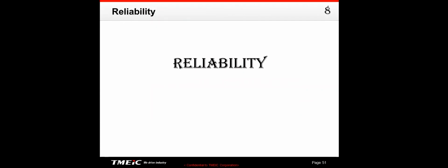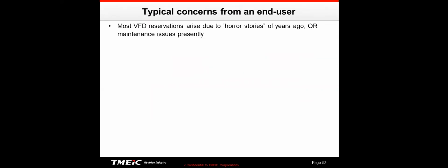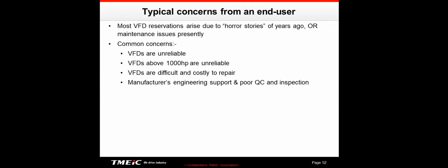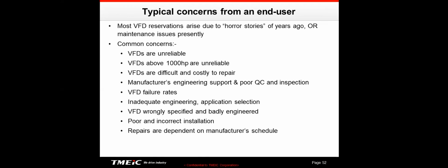Number 8, we're getting into reliability itself. In the past, people were scared of medium voltage drives because there were a lot of horror stories having to do with medium voltage drives. And common concerns was they're unreliable, the really big ones unreliable, they're scary, they're dangerous, they're difficult and costly to repair. And all of those issues have been solved, really. And they are much more reliable than a low voltage drive.